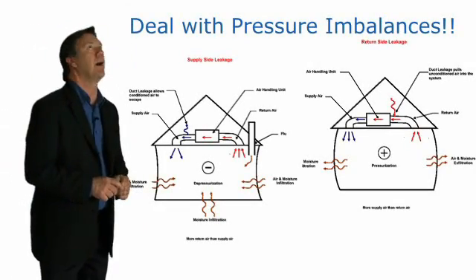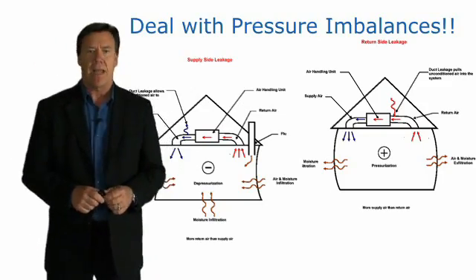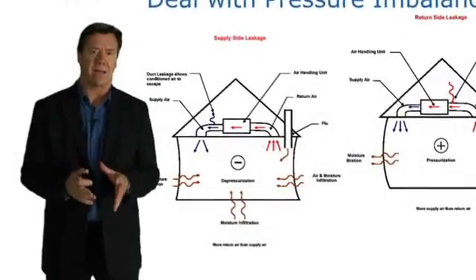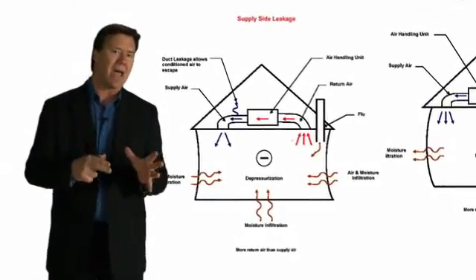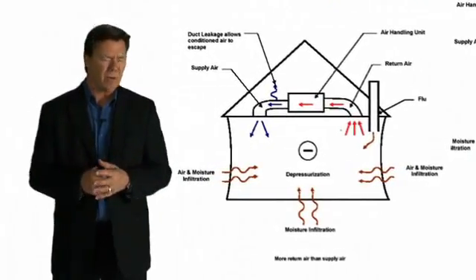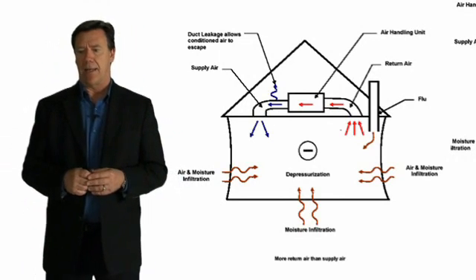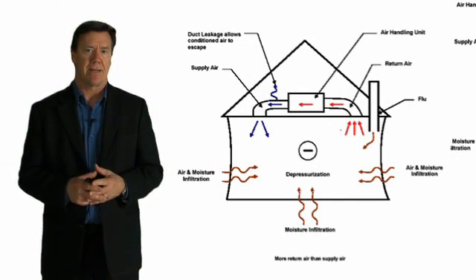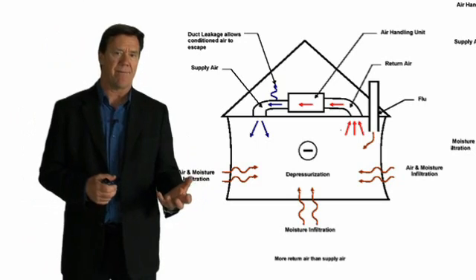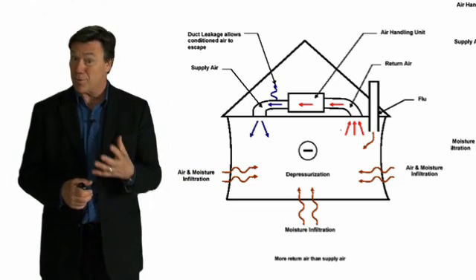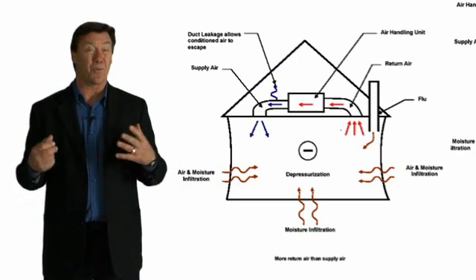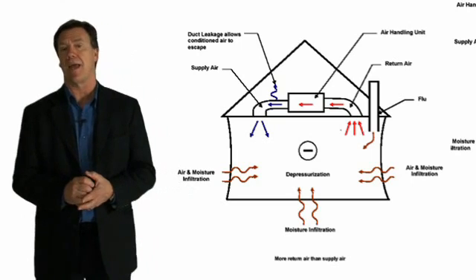We talked earlier about pressure differentials. If you look at the graphic on the left, this is what happens when we have supply duct leaks outside of the building envelope — they cause the structure to be under negative pressure. Let's say we have a 1200 CFM system with 300 CFM of duct leaks leaking into the attic. That means only 900 CFM is coming out of the supply registers, but the return air side is pulling 1200 CFM, so 300 CFM is leaking through all the cracks and gaps in the wall system.